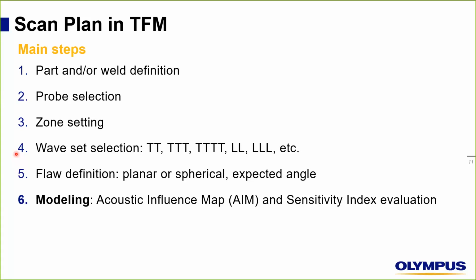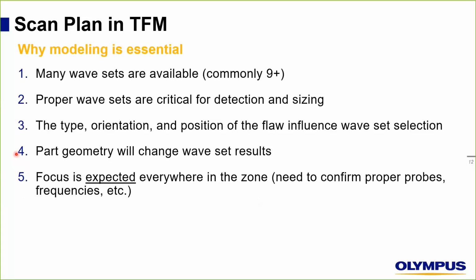Flaw definition. Actually, flaw definition is very important here, especially when we are using indirect mode or self-tandem mode. So we can have planar or spherical, and if planar, we can put the expected angle. Following these five steps, the software will generate an acoustic influence map, or AIM. This is what we call modeling, and we will see that modeling is very important, and it is essential actually.